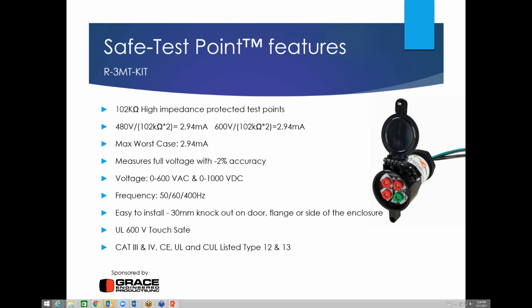Like anything, you want to obviously make sure that your voltage test instrument or your voltmeter is rated for the equipment you're going to be testing on. So this device is rated 0 to 600 AC or 0 to 1000 volts DC. And again, make sure that you're using the proper meter. And we get the question periodically, can they be used on different frequencies? And the answer is yes, anywhere between 50 hertz all the way up through 400 hertz. So that's the voltage test point.